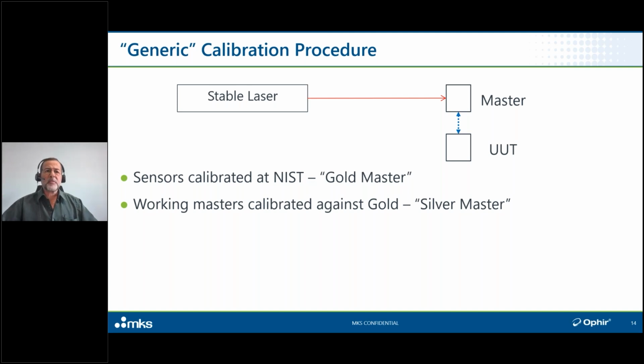We put the master in front of the stable laser and we take a measurement. We then quickly replace it by the sensor under test and we measure again. Even though we do it quickly, it might mean it takes half a second to do that switch. If the laser power actually changed during that half a second, then we're going to be calibrating the unit under test to read the same as the master, but the power is no longer the same as it was. So that would be a bad calibration. So we want the laser to be as stable as possible.